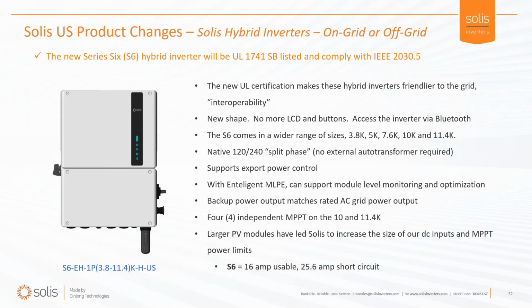You might also notice there are switches on the side of this device - one for DC, another for the rapid shutdown device - but there's also a manual bypass switch on the side of the inverter, so you can bypass the inverters completely and make sure all the loads in the home are connected together. This makes it easy to have no interruption when the service guy is out there making sure your hybrid inverter and battery are working as they should.